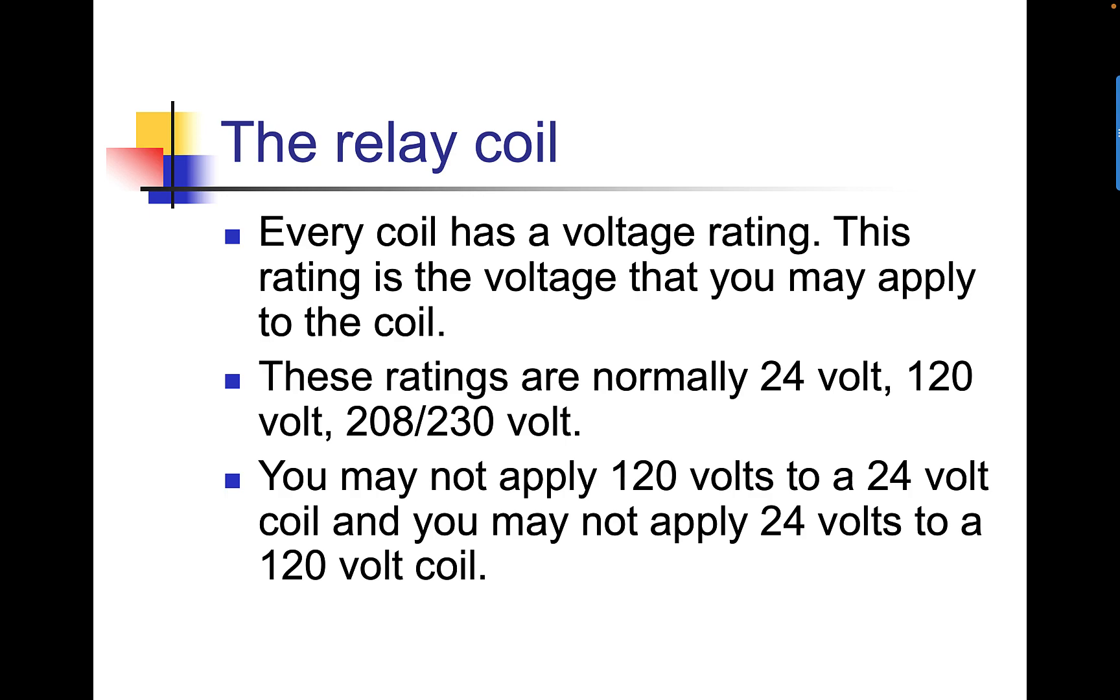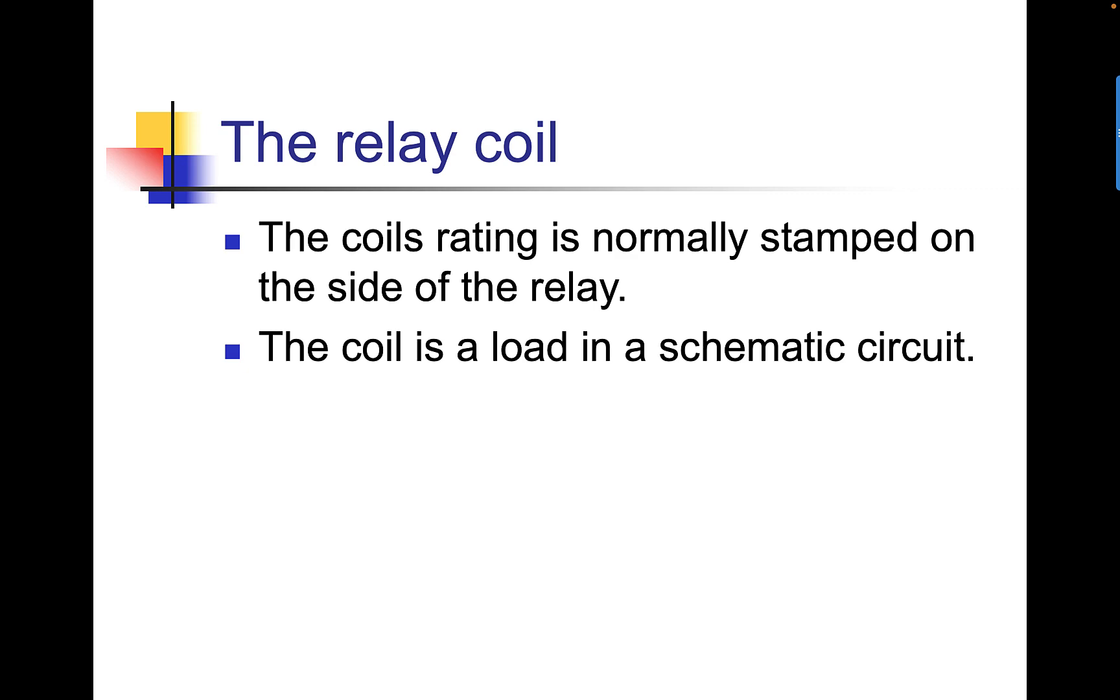The relay coil has a voltage rating. This rating is the voltage that you may apply to the coil. In HVAC, these ratings are normally 24, 120, or 208/230 volts. You cannot apply 120 volts to a 24-volt coil, and you can't apply 24 volts to a 120-volt coil. Bad things happen. You let the smoke out of things. The coil rating is normally stamped on the side of the relay.